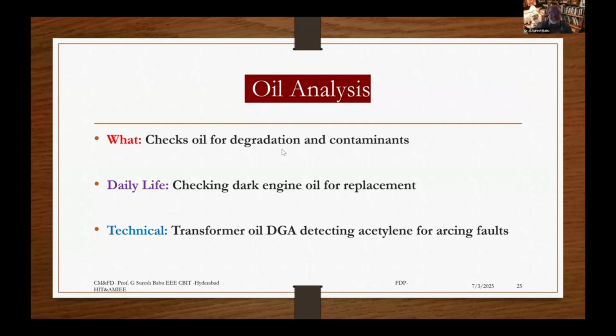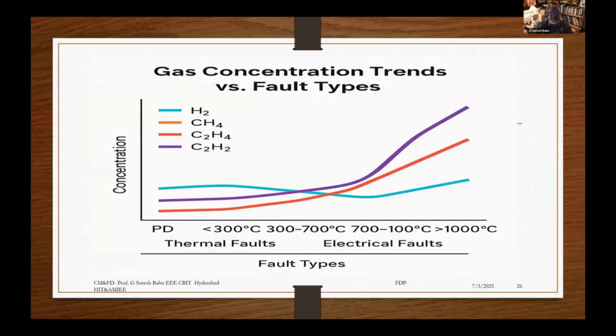DGA, detecting acetylene for arcing faults. So this is the graph where you find concentration and thermal and electrical faults for different gases: H2, CH4, C2H4, C2H2 type of faults. You'll be able to know exactly where the thermal fault is up to what level, and the electrical fault at what level, due to what concentration. This is only, as I told you, to give an idea about analysis, not any case study.